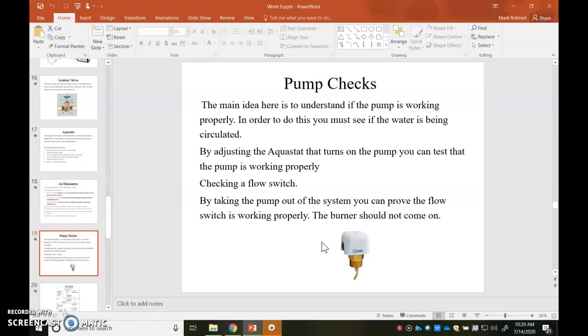Different scenarios or different boilers have some of them wait for the water to heat up to turn the pump on. Some of them turn the pump on as soon as there's a call for heat. They're all a little different. But sometimes there's a flow switch, and you'll see a flow switch sitting in the bottom of this PowerPoint here. And a flow switch is sensing that the pump is actually pumping the water around.